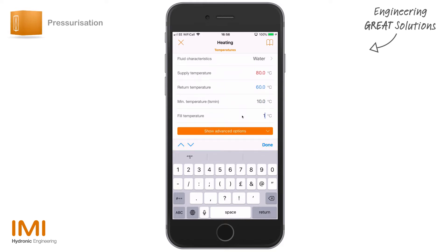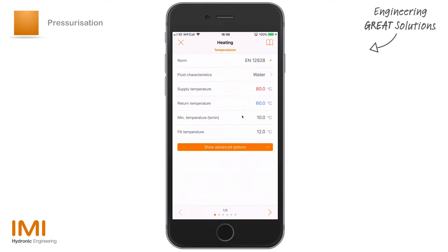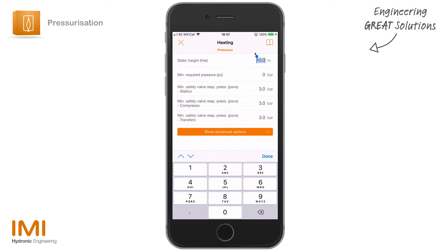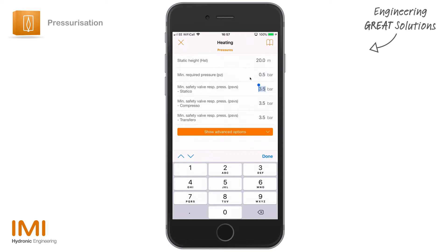We've selected these parameters and just need to click on the arrow to move through to the next section. This next section is all to do with pressure — it will allow us to predetermine what our minimum pressure required in the system is going to be. We've got 10 meters of static height here; let's say our building is a little bit taller, say 20 meters. If you've got a minimum required pressure — perhaps a piece of equipment requires it — let's say 0.5 bar, we're going to make sure we never drop below 0.5 bar in any given condition.